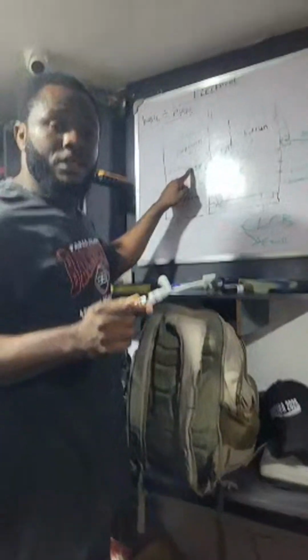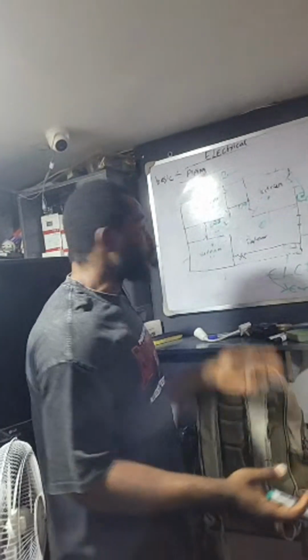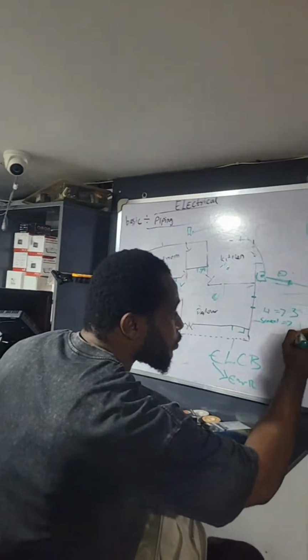What I'm getting at is that I want us to separate the ironing point. Assuming we put an ironing point here, because now we're working with advanced technology. Those who want to use small inverters will not carry up to iron. So they should have their circuit different. So this guy, 1 circuit. Kitchen, 1 circuit. And then the sitting room, 1 circuit. So we have 4. Isn't it?